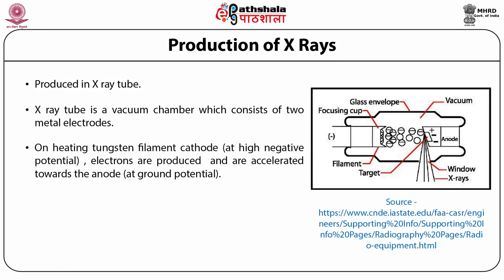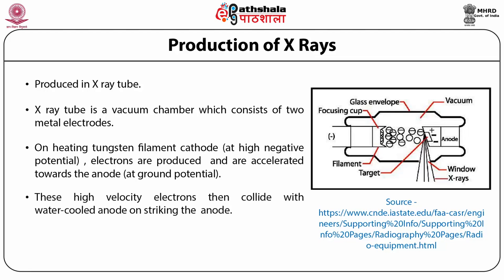The production of X-rays: X-rays are produced in an X-ray tube, which is a vacuum chamber consisting of two metal electrodes. On heating the tungsten filament cathode — present at high negative potential — electrons are produced and accelerated towards the anode at ground potential. These high-velocity electrons collide with the water-cooled anode. On striking the anode, loss of energy occurs, which is manifested as X-rays. Less than one percent of the electron beam is converted to X-rays; the rest is dissipated as heat in the metal anode. A diagram of the X-ray tube is shown on this slide.